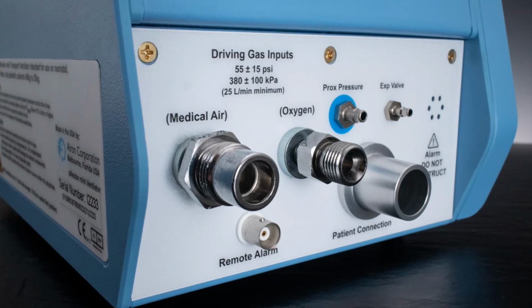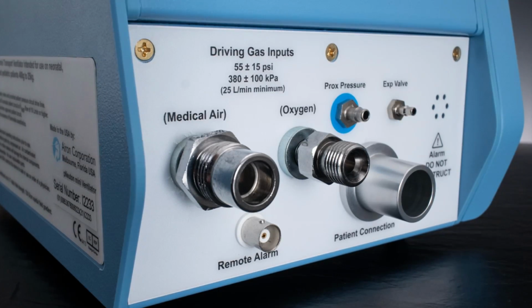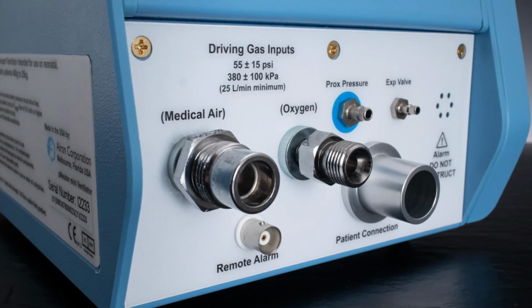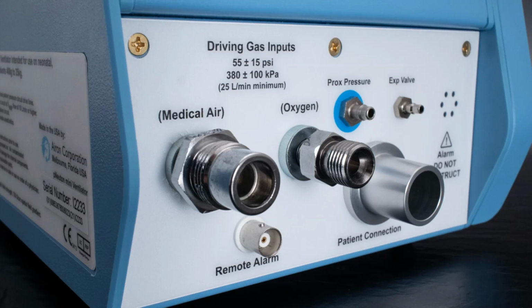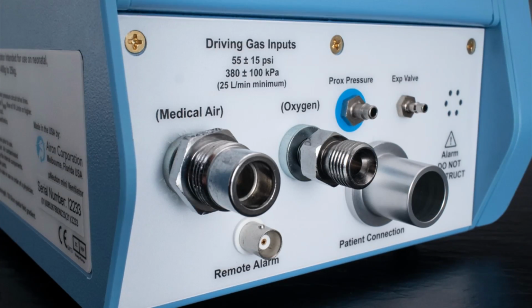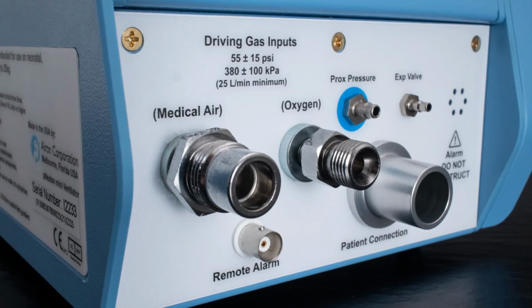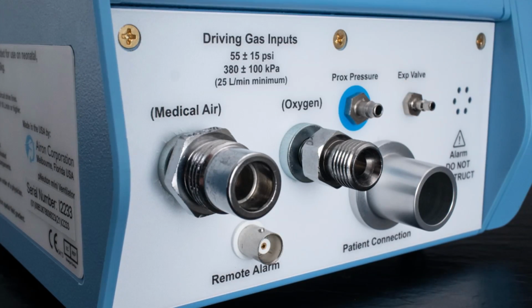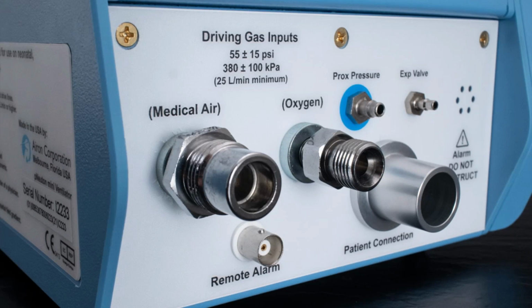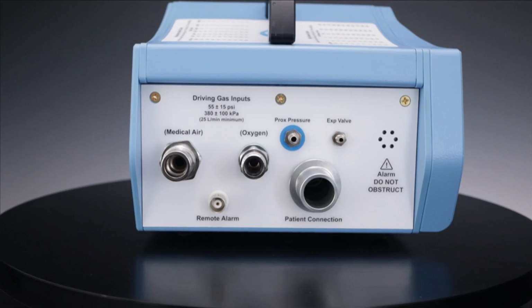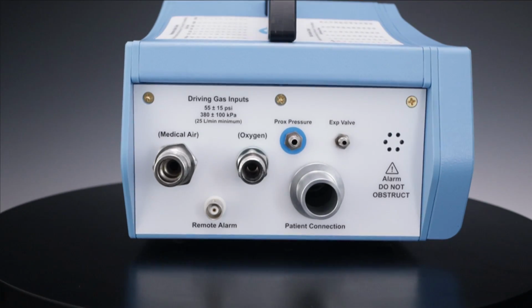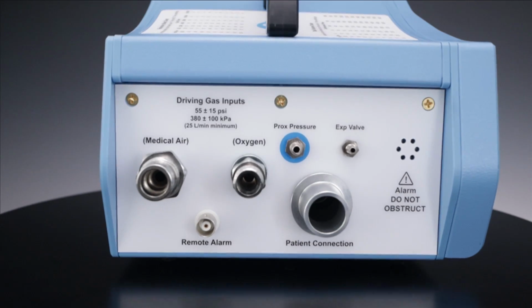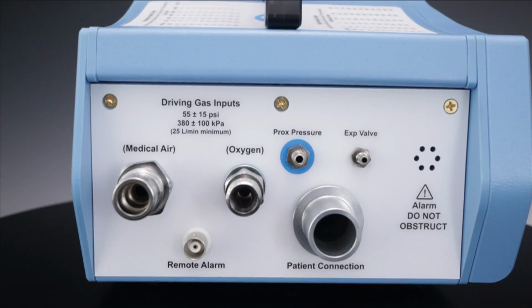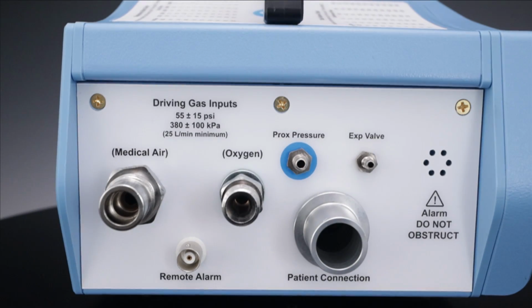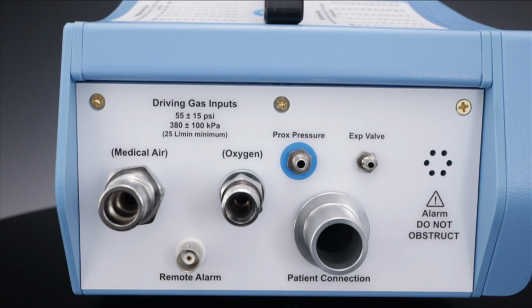Instead, the device requires high-flow oxygen and compressed air sources of 55 psi with a minimum flow rate of 25 liters per minute. Always ensure that the gas supply line is secure and operating at the proper pressure. The gas source must be able to maintain the required pressure delivery with flow up to 25 liters per minute available to the patient. If the driving gas pressure decreases below the required pressure due to flow demand, the low gas supply alarm will activate. Note that when the gas is first connected and flowing, the ventilator will alarm. This is normal. The ventilator will begin to function at the preset values.